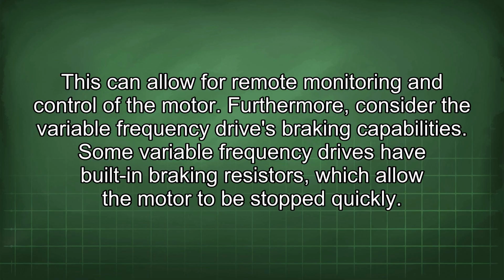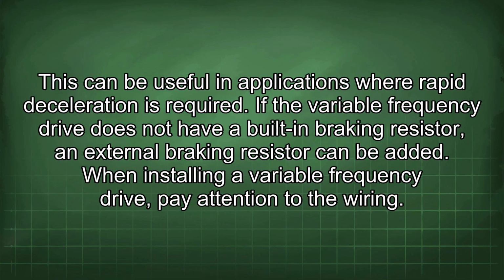Furthermore, consider the variable frequency drive's braking capabilities. Some variable frequency drives have built-in braking resistors, which allow the motor to be stopped quickly. This can be useful in applications where rapid deceleration is required. If the variable frequency drive does not have a built-in braking resistor, an external braking resistor can be added.